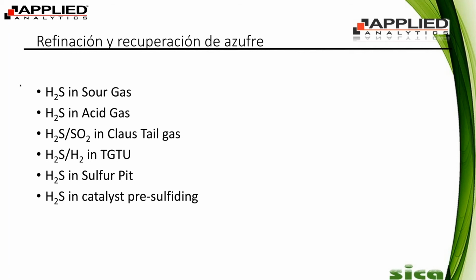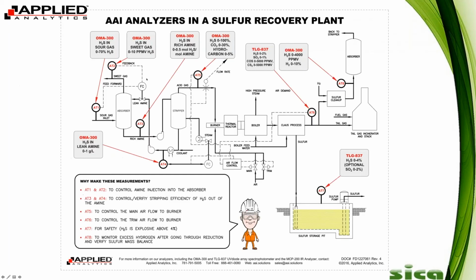And then next, and most importantly, I would say, our most successful application or product is the tail gas analyzer, which is our TLG-837. I'll talk about the products briefly at the end, but you can see at AT6, we measure H2S, SO2, and air demand. For those of you who know about the tail gas analyzer, you know this is key in an SRU. It's in every single SRU around the world. It's key for efficiency purposes. Basically, what you do in tail gas is monitor the tail gas stream of the Claus process to ensure that the ratio of H2S to SO2 is 2 to 1, because that's vital for efficiency purposes.